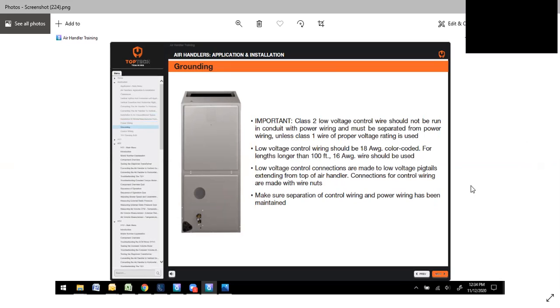Grounding, important. Class 2 low voltage wire should not be run in conduit with power wiring, must be run separate from power wiring unless class 1 power wiring rating is used. It's a good idea not to mix those because you can get some noise interference, especially if you're dealing with a communicating system. These particular air handlers are not. Low voltage control wiring should be 18 gauge, no lengths longer than 100 feet. For anything longer than 100 feet, 16 gauge wire should be used. Don't use speaker wire. Don't use that really thin, cheap thermostat wire. Use the proper 18 gauge solid wire.